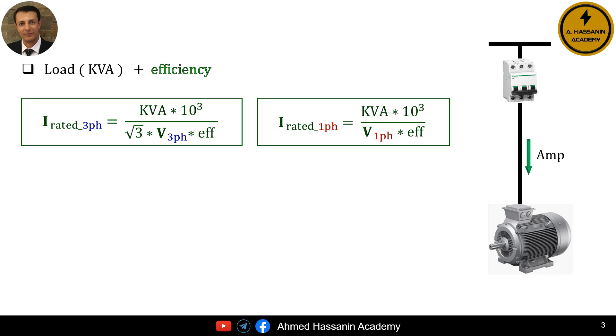For a single-phase dynamic load or single-phase motor, the equation for the rated current of the motor load is the rated power value in KVA multiplied by 10 cubed, divided by the single-phase rated voltage in volts and the motor's efficiency.